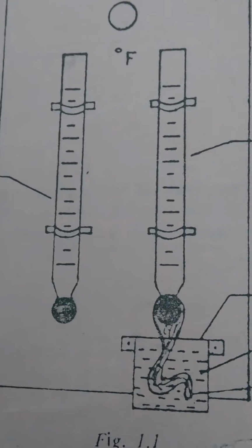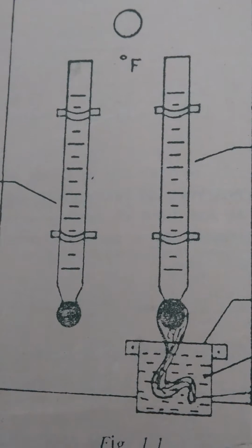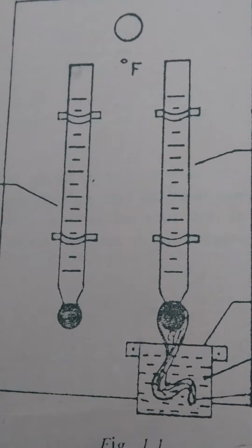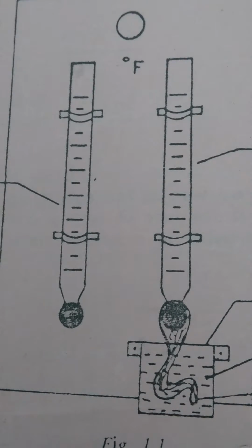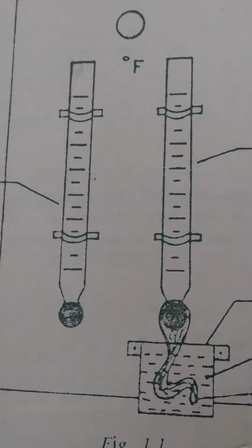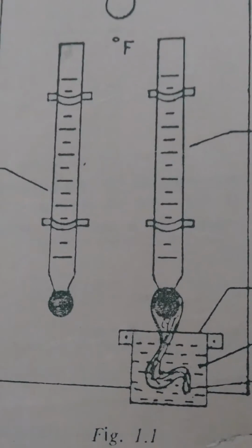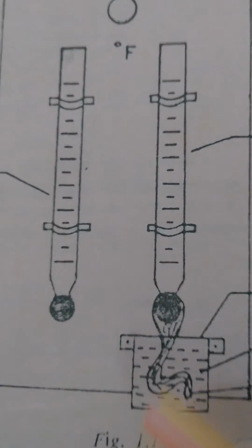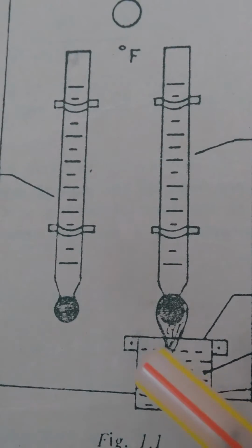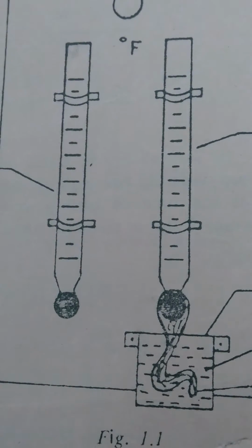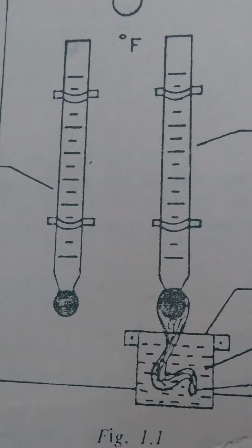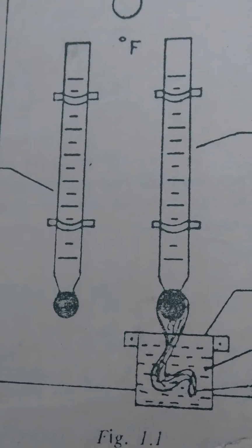Now, regarding the working, the wet and dry bulb hygrometer consists of a frame on which two identical thermometers are mounted. The bulb of one of them is covered by a muslin sleeve, which is dipped into a reservoir of distilled water. This is known as the wet bulb thermometer. The bulb of the other thermometer is uncovered, and from that thermometer the room temperature or dry bulb temperature can be noted.